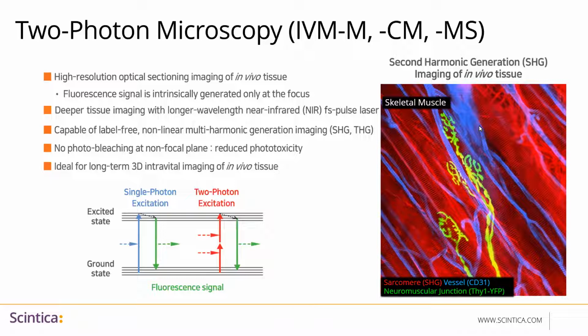The 2-photon technique uses near infrared excitation light, and since a lot of tissues are effectively transparent at these wavelengths, the background signal is strongly suppressed. So the combination of these effects increases the penetration depth and reduces the photobleaching of your sample. So that's why often for deep tissue microscopy, 2-photon is used instead of a confocal.